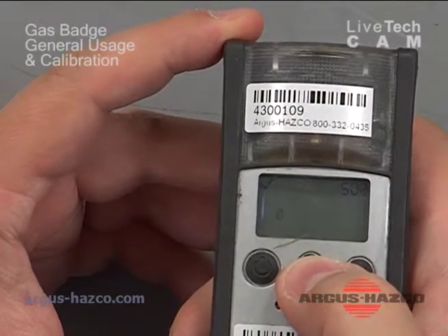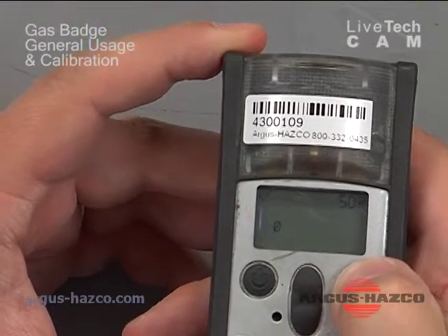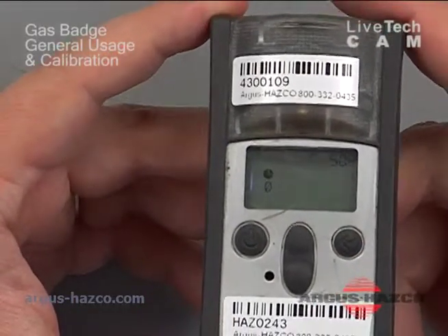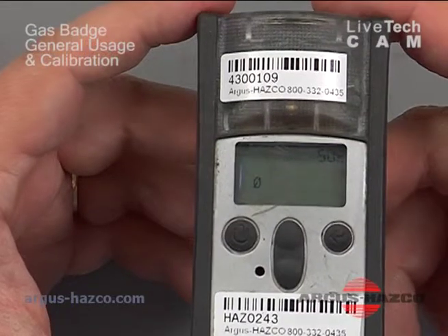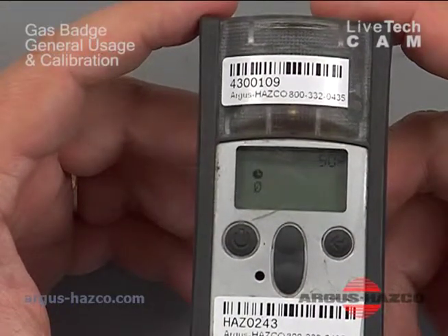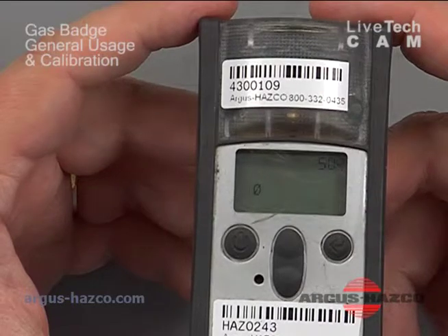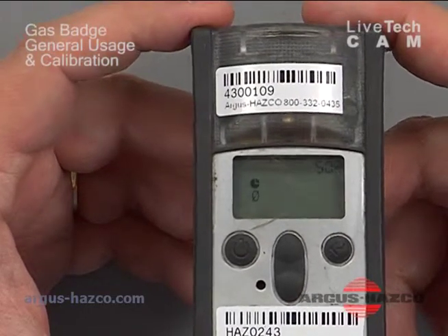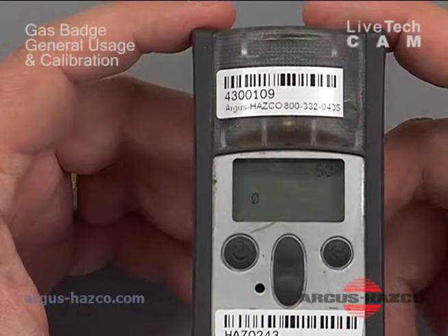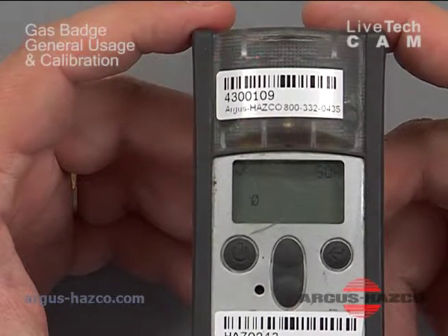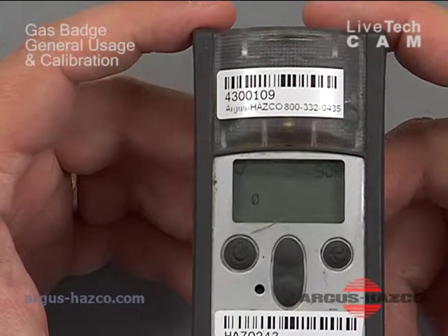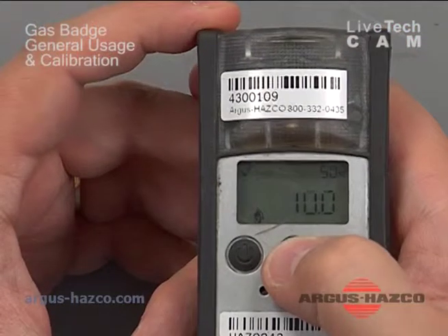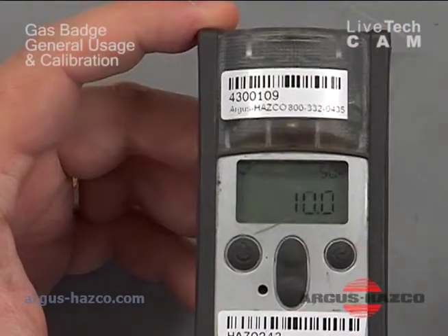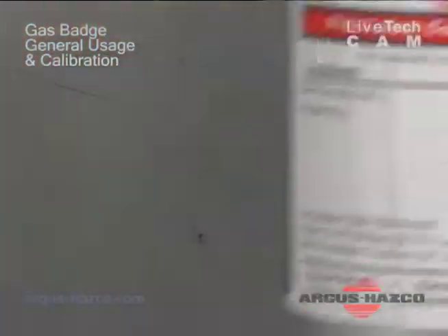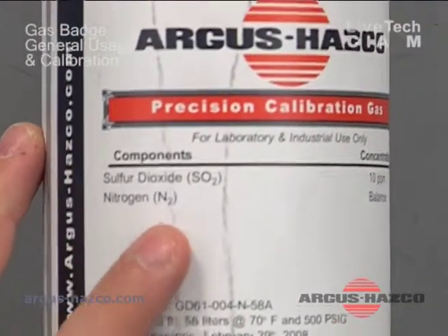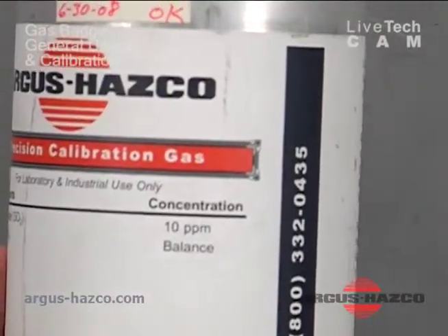And right here it's flashing the 0. If you hit enter and acknowledge, it's going to give you a clock, and it's trying to do a fresh air 0 of the sensor. The sensor will need a baseline to tell it what 0 is as compared to the span gas you're about to calibrate it against. So you need to make sure you're in a fresh air environment, nowhere where you're smoking a cigarette or something like that. It can throw off what fresh air 0 truly is. So now it's zeroed, and it's asking for 10 ppm of the span gas. And on your cylinder, you'll see that it's sulfur dioxide, 10 ppm.